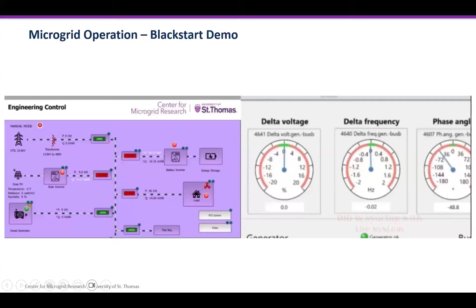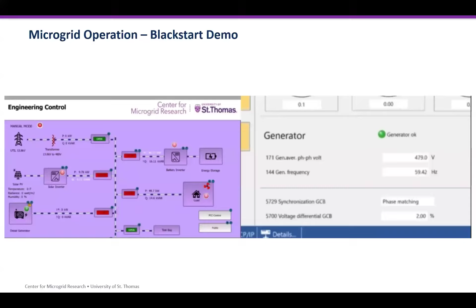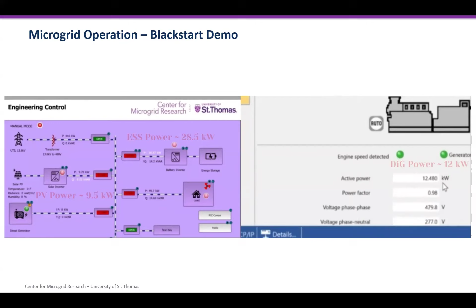So the breaker at the generator will be open until it is synchronized. After it is synchronized, it is closed and it can feed power to the load. So now they are synchronized, it's feeding power. As you can see here, it's around 12 kilowatts of power from the generator, and we have ESS 28.5 and 9.5. This is the 50 kilowatts required by the load itself.